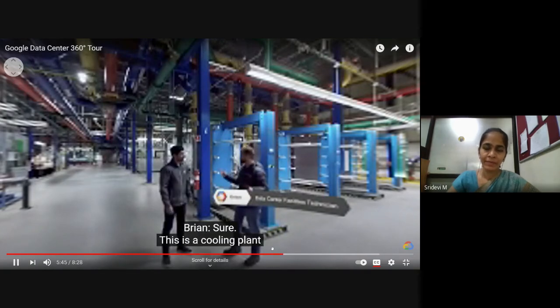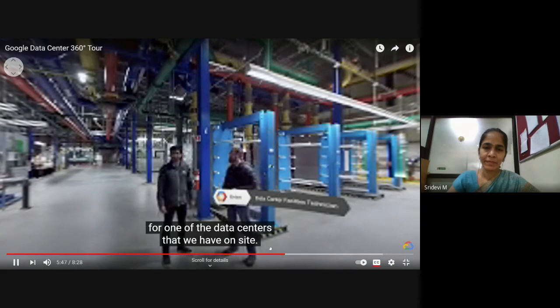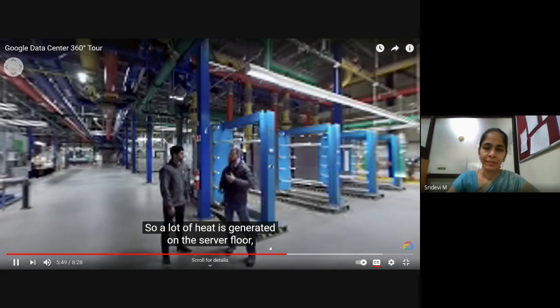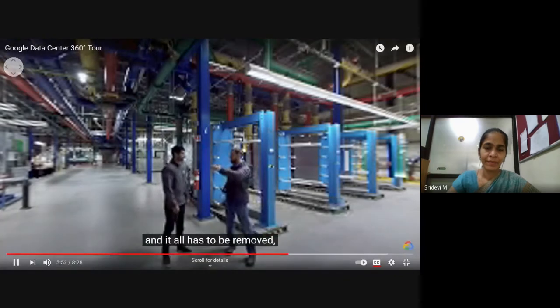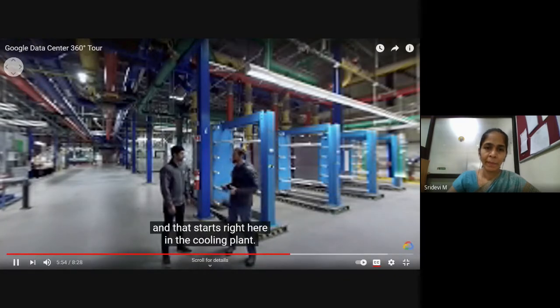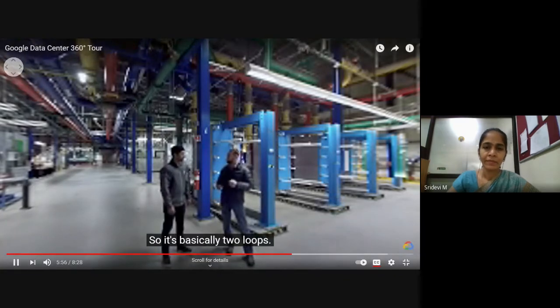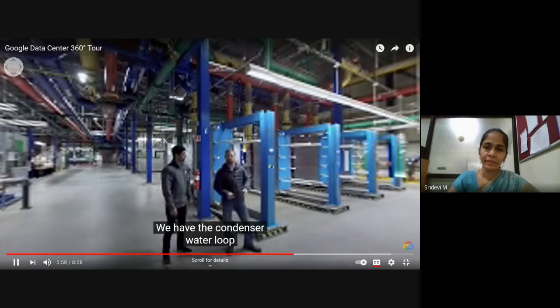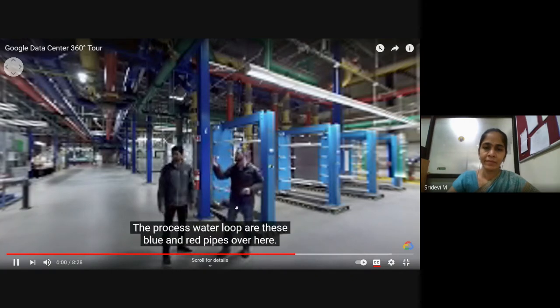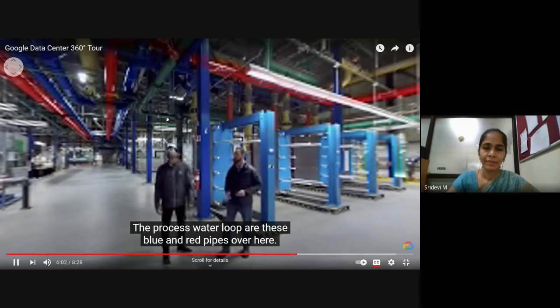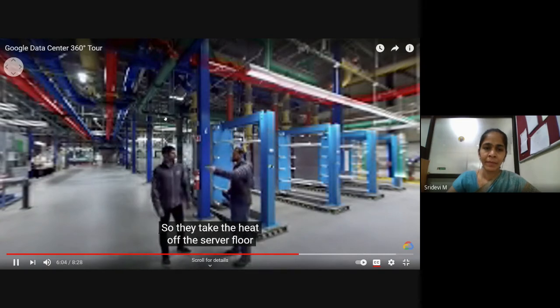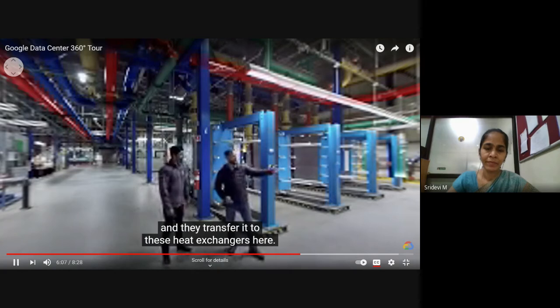Sure, this is a cooling plant for one of the data centers we have on site. A lot of heat is generated on the server floor, and that all has to be removed, starting right here in the cooling plant. It's basically two loops: the condenser water loop and the process water loop. The process water loop is these blue and red pipes over here, which take the heat off the server floor and transfer it to these heat exchangers.